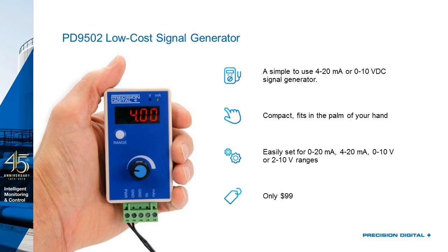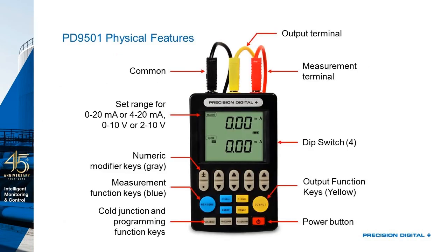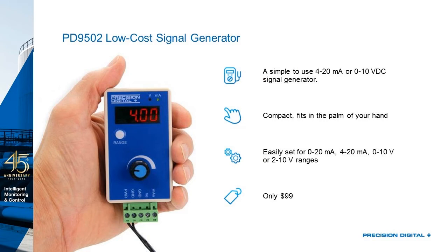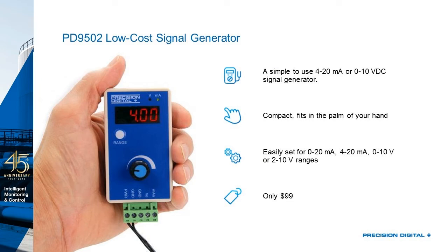Here we have the 9502 low-cost signal generator. This is the lower cost version of that 9501 we saw earlier, and it's designed very simply to produce a 4 to 20 milliamp or 0 to 10 volt signal. It's very compact, even smaller than the 9501. This is actually the hand of one of our marketing team here, so this isn't some stock image we photoshopped together - it really is that small, and it's just really convenient to stick in your pocket and carry around with you, although you do need to power it. It's not battery powered. It's an easy way to get a 0 to 20 milliamp, 4 to 20 milliamp, 0 to 10, or 2 to 10 volt output for only $99.